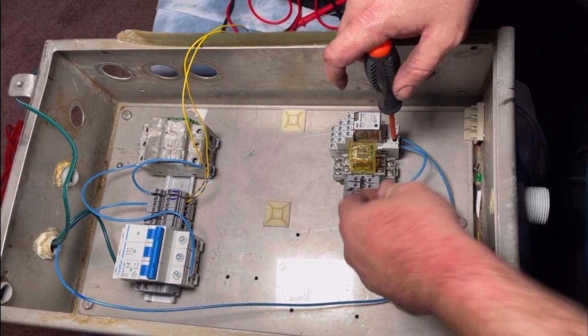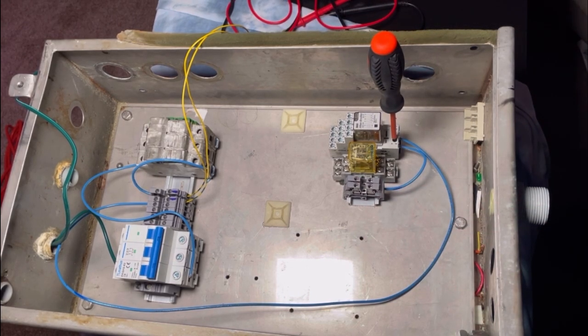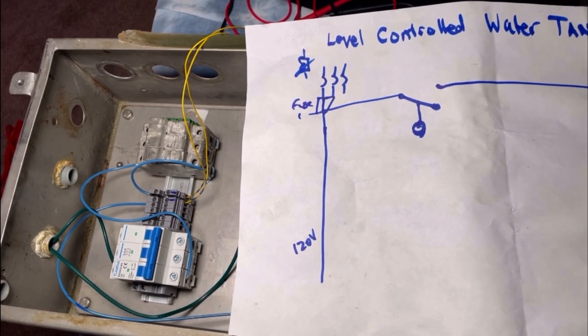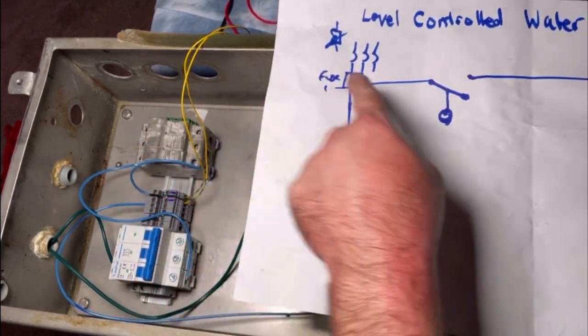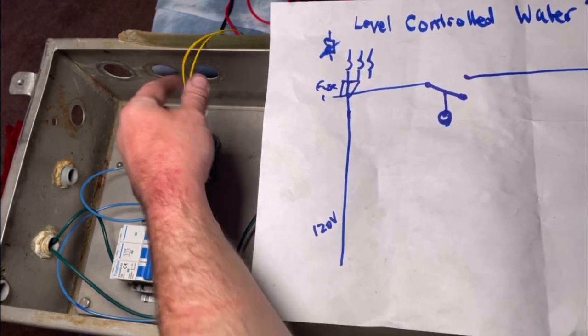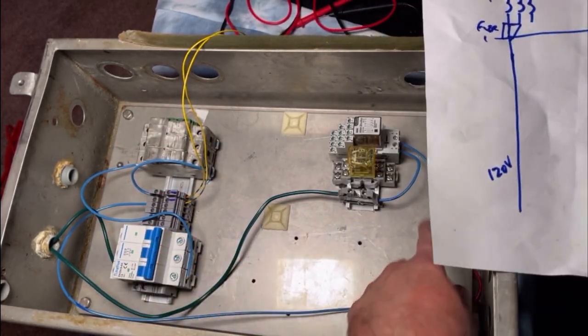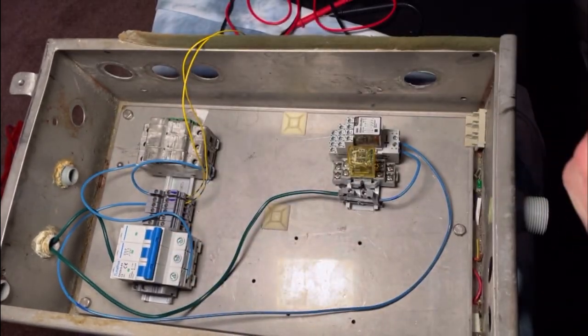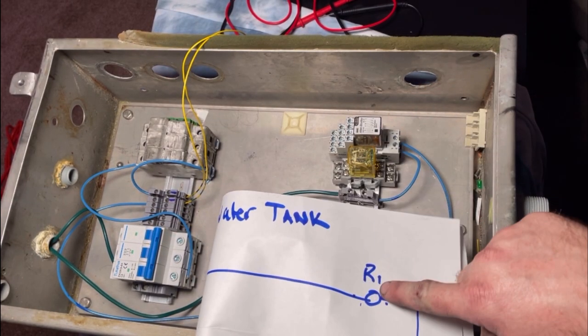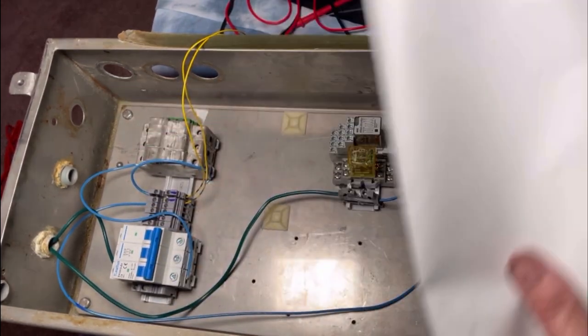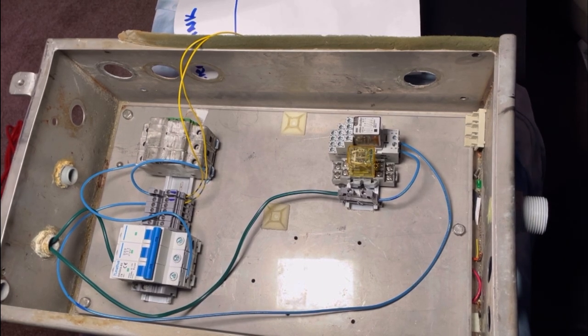So run my A2 to this point right here. This is what I'm using for my neutrals. All right, so I got my circuit breaker, then fuse, then float switch, running around here through my relay, then A2 down to neutral. And back to, in this case, it's going to go to an outlet in the wall, which is going to go to a main circuit breaker, which has a ground in there. The neutral and the ground will bond together inside of that circuit breaker.